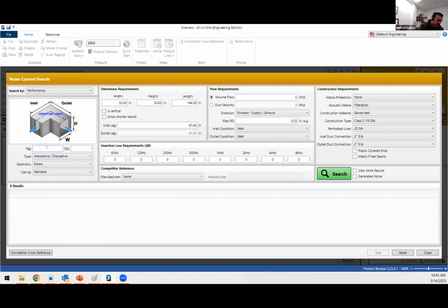All right. So discharge, and then you select by performance. In this case, it's by design criteria, right? You can play with the leg lengths of your elbow. You might not have a lot of room on the vertical, so you might want a different leg length. In this case, because the width is 50, to make it an elbow you need a little bit of distance to turn it. The minimum distance as a standard is 7 inches. So this leg in here, the smallest you can make it, if it's 50 inches wide, is going to be 57.